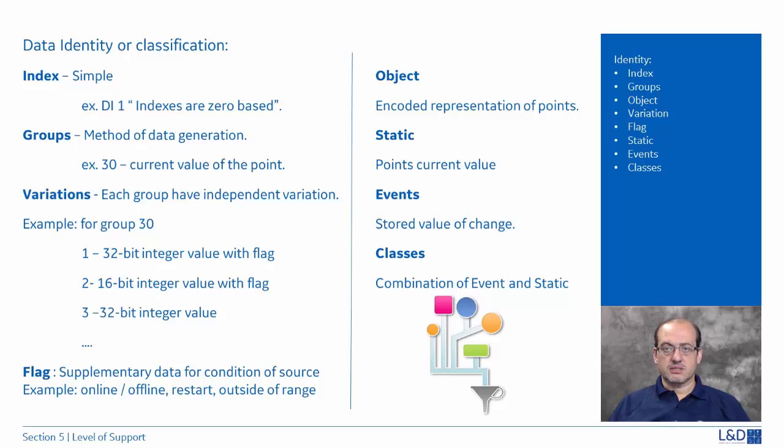One of the key things in communication in DNP is how do we refer to the data that's being generated: a voltage measurement, a current measurement, a status of a breaker. All of this information that is available in our substations is basically translated into digital data, either a digital input or a digital output, an analog input or an analog output, a counter, or a status of a device.